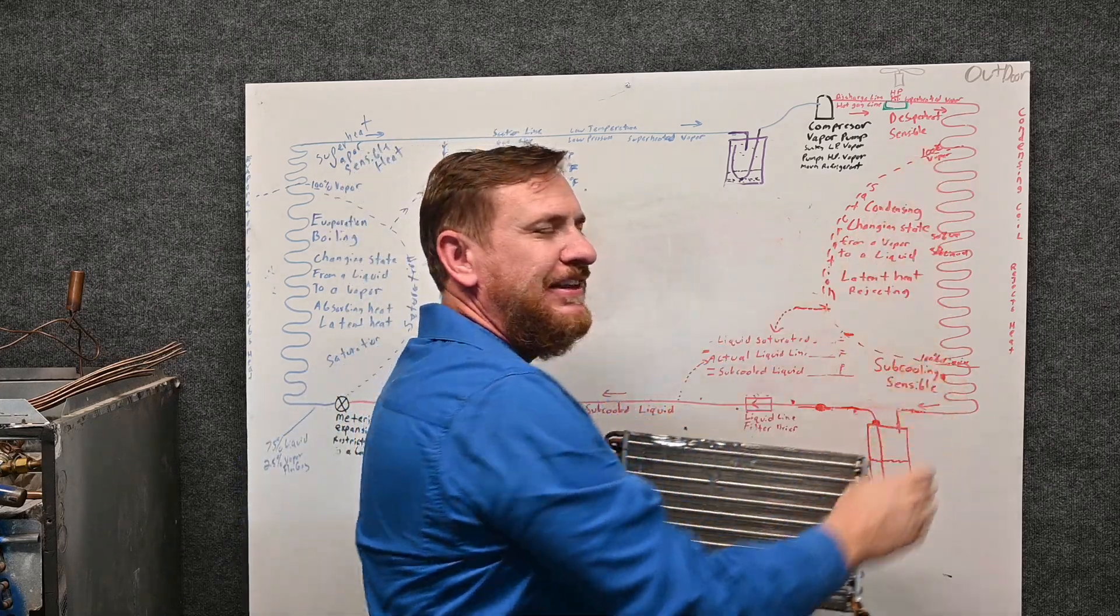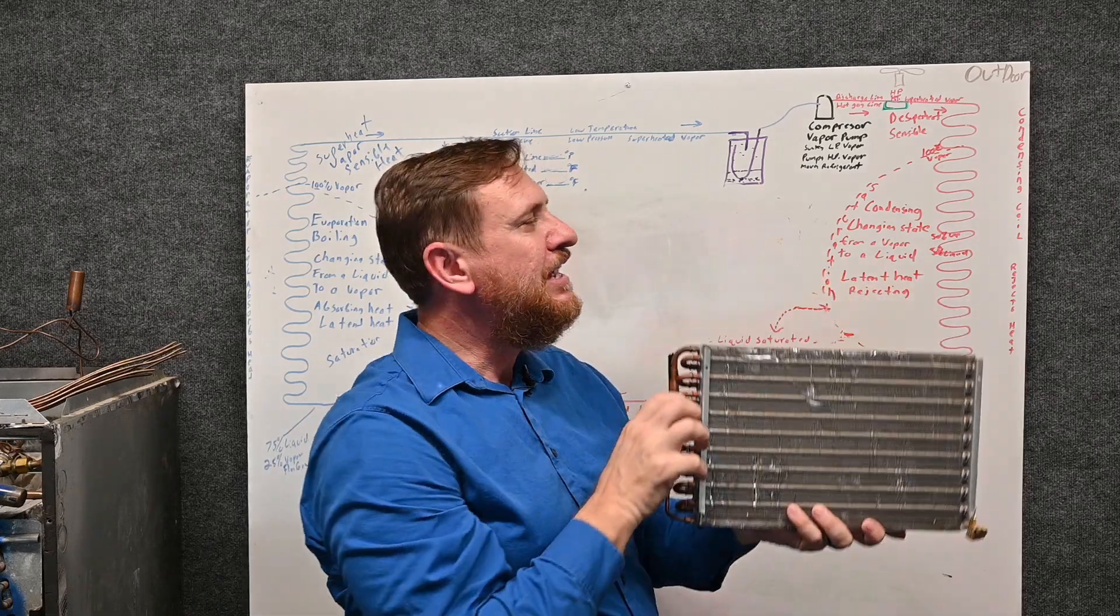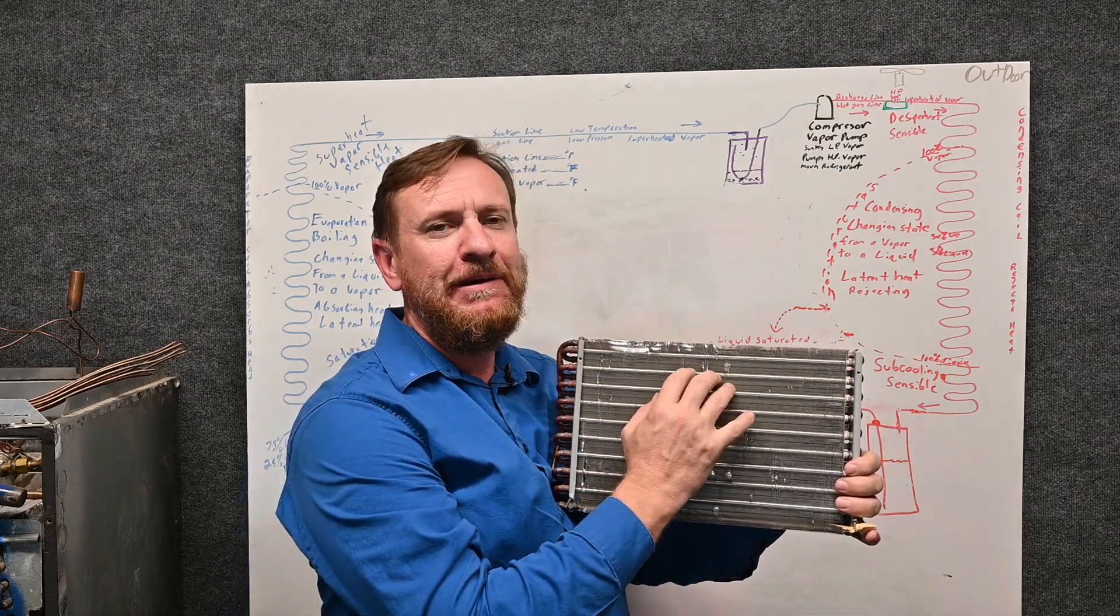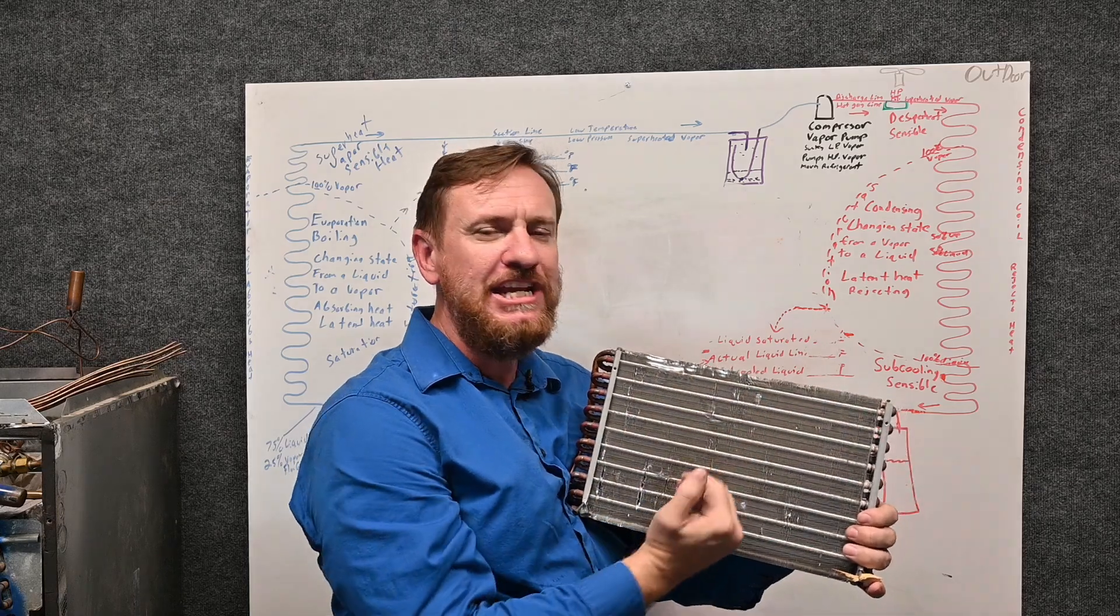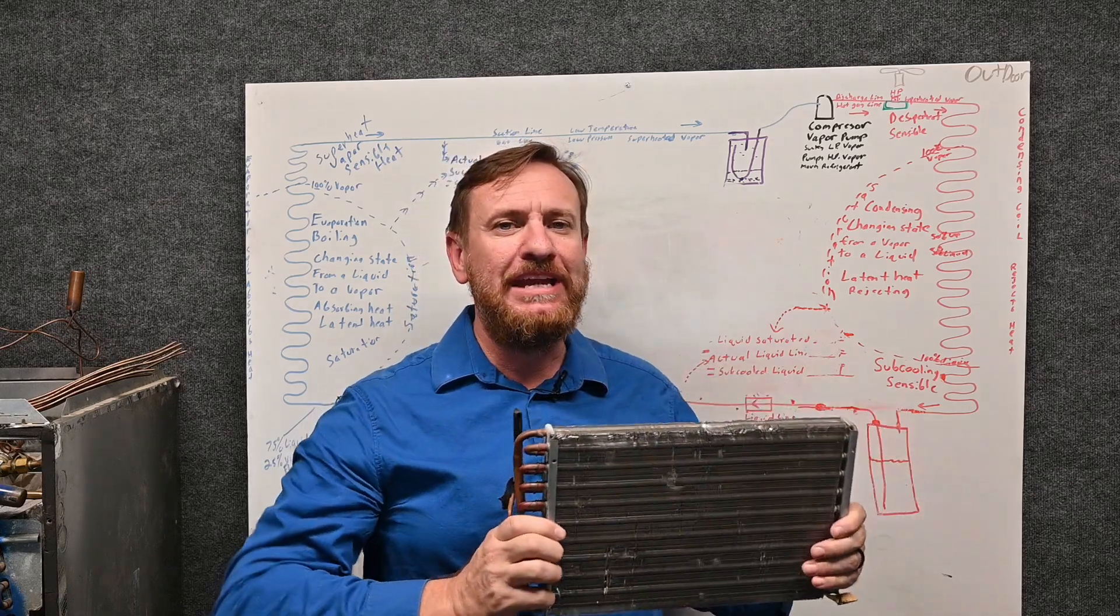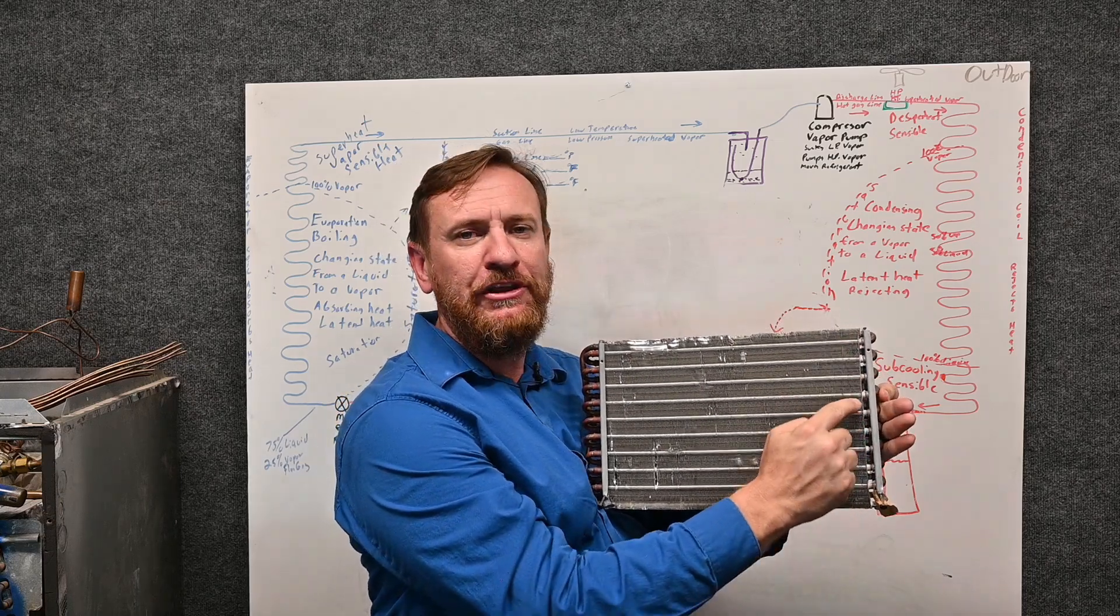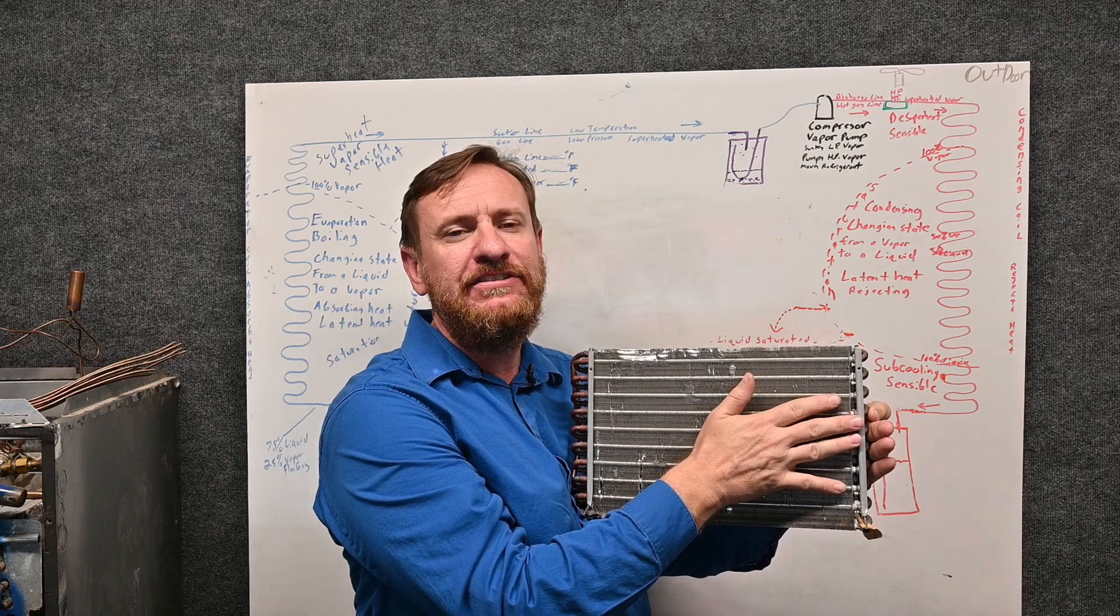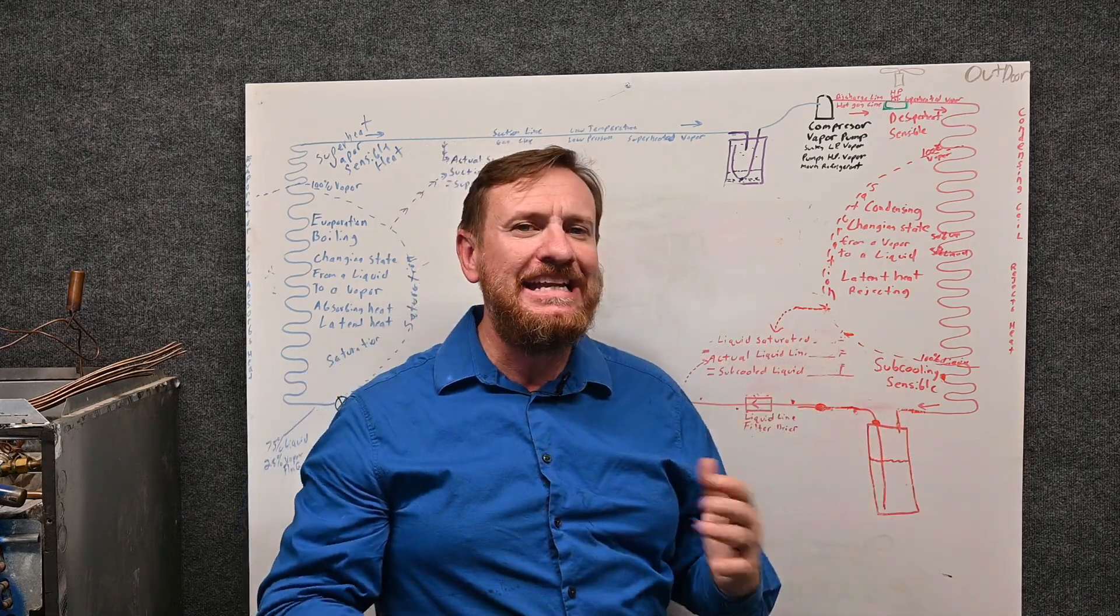Now, the middle of this—this is key. The middle section of this condensing coil is where we're changing state. We're condensing the refrigerant, changing state from a vapor to a liquid, and it's rejecting tons of latent heat. That's change of state, that's the hidden heat—we can't measure it. The temperature here and here, or all the way through, is going to be about the same temperature because it's a change of state without a change of temperature. Tons of latent heat. Remember that latent heat is so important.